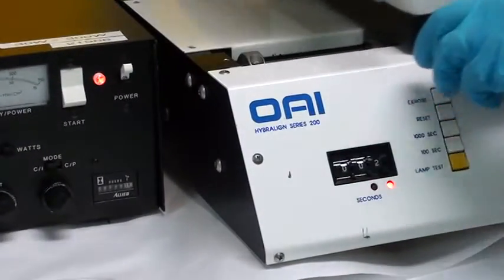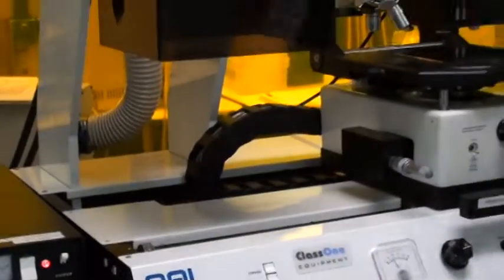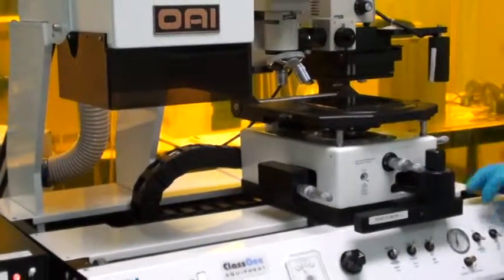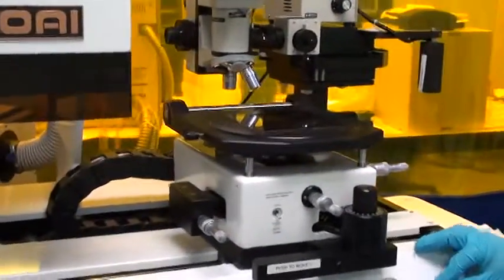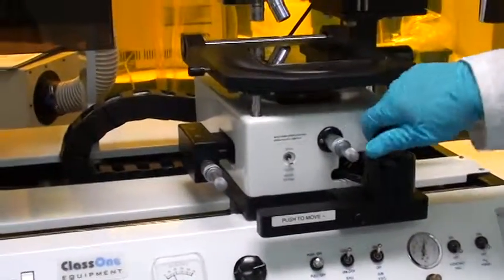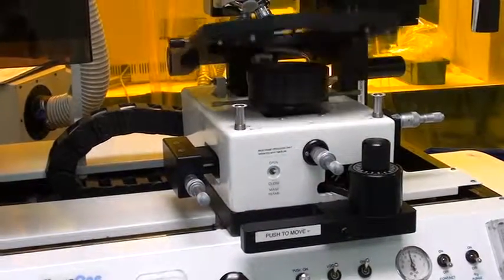And then we move our wafer back over to the aligned position. If we had done a vacuum contact, we would run a purge, which would then purge all the vacuum out of that area. We would then lower our chuck down, and we can lift up our mask holder.